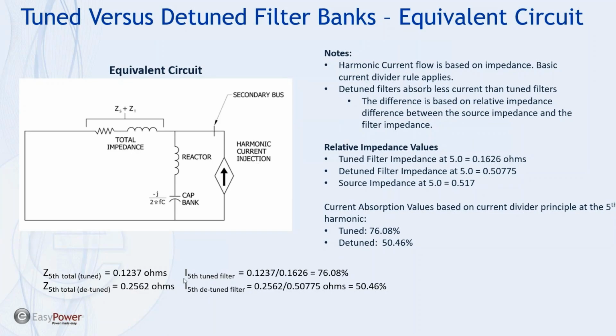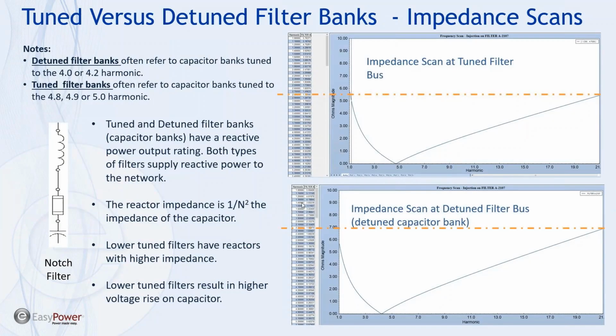So you can see that for the tuned filter, we actually will take in about 76% of the fifth harmonic current. The detuned filter will take in 50.46%. You could also do this using EasyPower and just do the calculations, but I think it's important to understand what is going on from a circuit standpoint. So the detuned filter also offers a relatively low impedance path for fifth harmonic. And if you think about what's going on here, we look at the impedance curves here, as we go up in frequency, that relative difference becomes less and less.